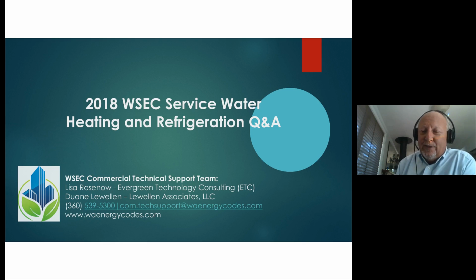That's a great question. And putting together the slide deck, I tended to look at that. If it's a change of use from FS or U to other than FS or U, you have to fully comply. And if your change of use is from something other than R1 or R2 to R1 or R2, and you have high input service water heating, your total capacity of your water heating system is greater than 1 million BTU, you would need to comply with the service water heating. That's my general intent. Although if you look at the specific language, it says new buildings, but then we have chapter 5 that basically says that changes of use have to fully comply. So I'm kind of making my own judgment call here on intent.